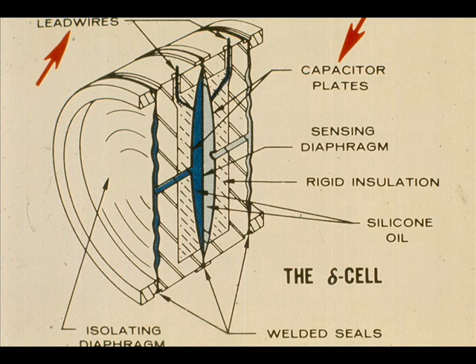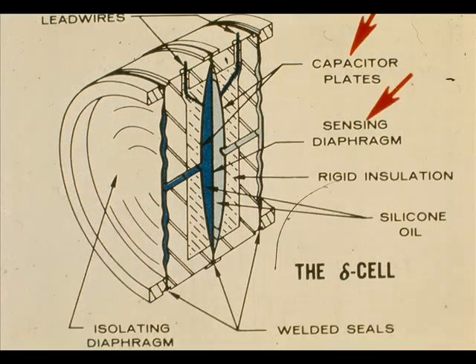Take a close look at the capacitor plates and the lead wires attached thereto. The capacitance between either of the plates and the sensing diaphragm is approximately 150 picofarads. An oscillator drives the sensor at approximately 50 kilohertz and 50 volts peak to peak.